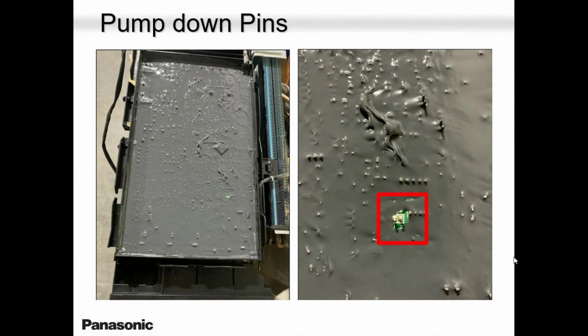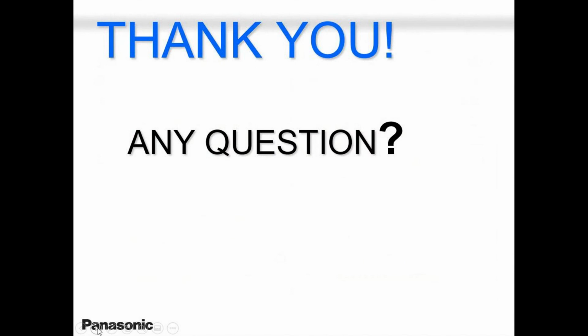Okay, that's your 4-way valve there. Down over here is your reactor. On a 12,000 BTU, 9,000, 15, and 18, the reactor is over here. You will see it open. Over here, it's covered because of frost, ice, and you name it. That's your condenser fan motor. Then, at the top of this board, there is a plastic cover. When you open up the cover, you will see the board is coated with this kind of waterproof material. Okay, I don't tell you to pour water on it, please. Do not do that for testing. It is protecting against snow, rain, and you name it. And it is protecting all year round, no problem.